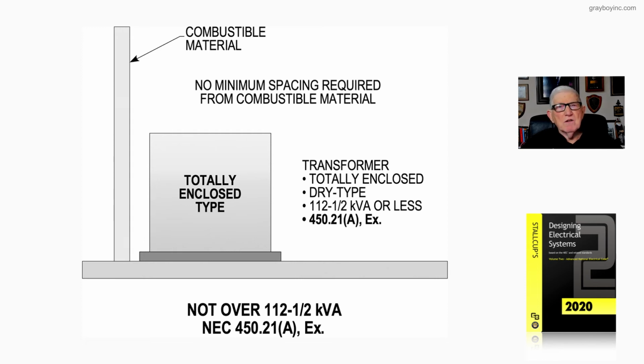Dry type transformers rated 112.5 kVA or less and 1,000 volts or less shall not be required to have a 12-inch separation or barrier if they are completely enclosed except for the ventilating openings. And that's exactly what our figure 20-24 is illustrating.